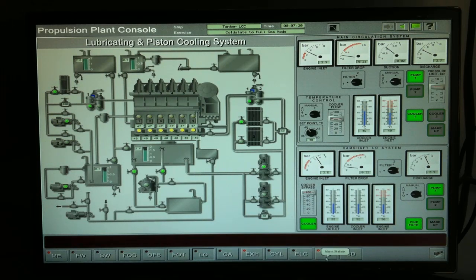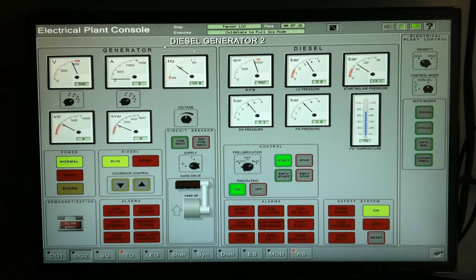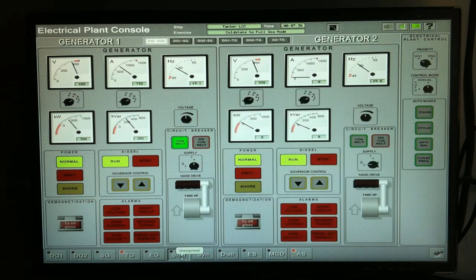Okay, so for the meantime, we proceed back to the generator. Once you have generator number 2 already warmed up and it has voltage and hertz, we need to synchronize, share, and balance 2 generators. So we go to the sharing page. You need to adjust the hertz in order to connect it to the main bus bar. So the incoming generator should be reduced slightly. Reduce the hertz by using the governor control. Once you have equal hertz on both generators, you could already connect it to the main bus bar. Once it's connected, you balance the generators.